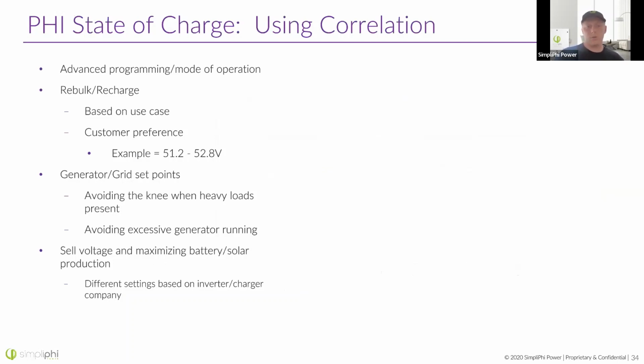So this also kind of influences your set points. A lot of customers are asking us, how do we set the rebulk voltage? Really, it depends on your preferences. I often see them as low as 51.2 to as high as 52.8. If you want to be keeping your battery more full all the time, use 52.8. So it'll initiate a charge anytime your battery drops to 52.8. If you want to do less charge cycles, then let your battery discharge a little further and let it go to 51.2. Now, I personally have my system at 52.8 because I like to keep it full.